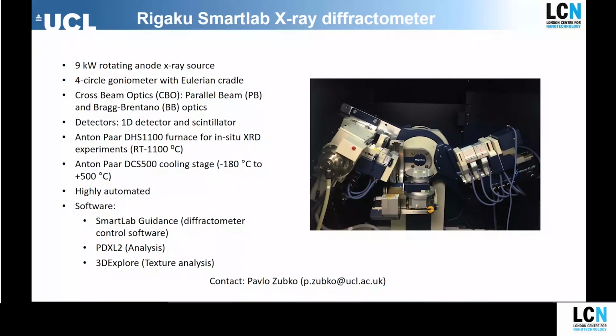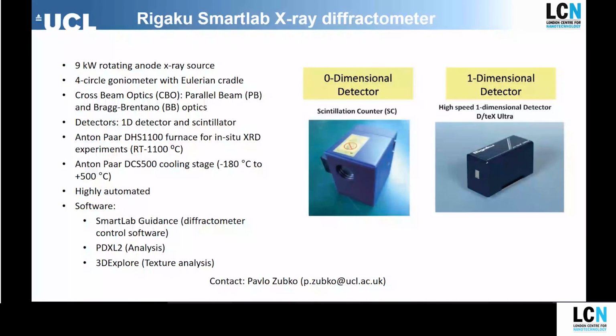So it has a cross-beam optics module that allows you to easily switch between a parallel beam configuration for, say, measuring thin films, or Bragg-Brentano focusing optics for powdered samples. And we have a number of monochromators for different trade-offs between intensity and resolution. On the detector side, there's a couple of detectors. There's a 0-dimensional detector, a scintillation counter, and there's also a high-speed 1-dimensional silicon strip detector, which is very good for doing quick reciprocal space mapping.